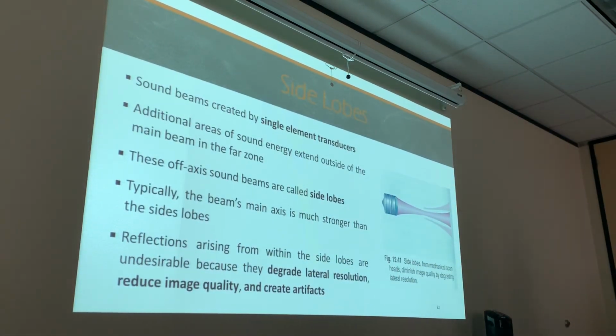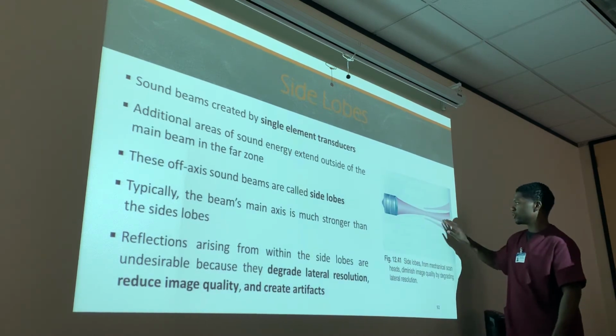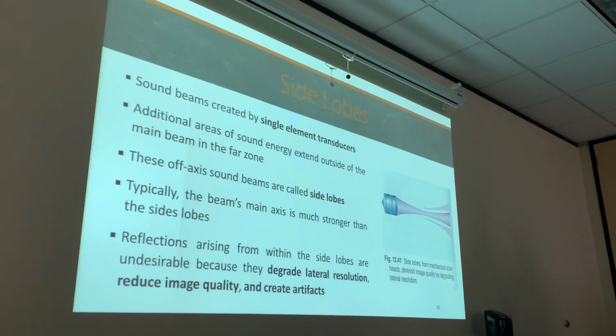Speaking of elevation and resolution, let's talk about these side lobes, guys. Side lobes are created by single element transducers. Fact 1, side lobes are created by single element transducers. This is all we've been talking about so far, single element disc-shaped transducers, right? These side lobes are actually additional areas of sound energy that extend outside the main beam into the far zone. See, this is our main beam, but we also have these additional weaker sound beams that also contribute to the image. These off-axis sound beams are called side lobes. Typically, the beam's main axis is much stronger than the side lobes. The main beam is way stronger than the side lobes, but these side lobes create noise on our image that takes away from the detail.